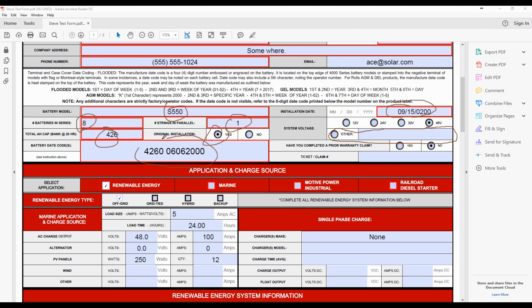Battery date codes are on all the batteries. Prior to a couple years ago, all the Series 4000 batteries had a 4-digit date code, something like 4260. That means the battery was manufactured on the 4th day of the week, the 26th week of the year, and the 0 is the last digit of the year. So it would have been manufactured roughly around June of 2000, on a Thursday.